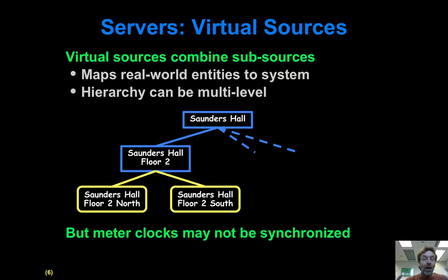But oftentimes the way that data is collected is not from just a single meter attached to that entire building; you might have sub-metering. So you might have separate meters installed for the various floors and so forth of the building, and those all get collected together to provide, in aggregate, information about individual floors, individual towers in a building, or the actual building as a whole.